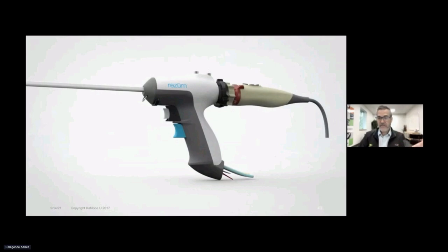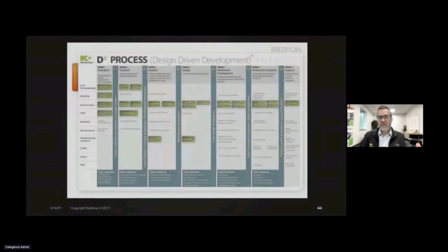So we would do verification and validation in your design controls, but from a usability standpoint, we would do our usability validation with this device through what we call a summative study. And this is where we get 15 or more users. They all use this device in a real world situation. And we document whether all of those potential hazard, use hazard situations are mitigated and are acceptable at the end of their use. And we record that, and we have a usability report that comes out of a summative study. And then we have a usability engineering report that sums up the entire thing at the end. So that's how we go through this process.